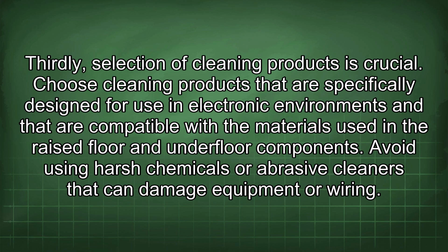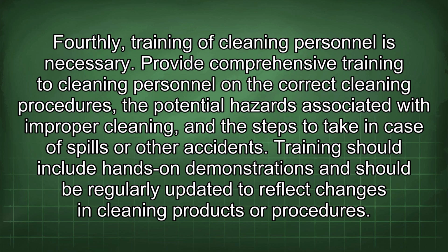Choose cleaning products that are specifically designed for use in electronic environments and that are compatible with the materials used in the raised floor and underfloor components. Avoid using harsh chemicals or abrasive cleaners that can damage equipment or wiring. Fourthly, training of cleaning personnel is necessary. Provide comprehensive training to cleaning personnel on the correct cleaning procedures, the potential hazards associated with improper cleaning, and the steps to take in case of spills or other accidents. Training should include hands-on demonstrations and should be regularly updated to reflect changes in cleaning products or procedures.